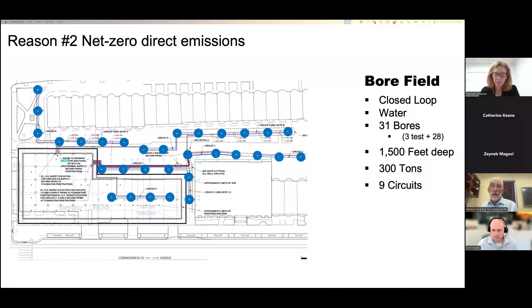The system is sized to provide 300 tons of cooling, or 90% of the thermal needs for the building. Electric backup boilers and chillers are designed to cover that last 10%. Early in the design process, the team looked at what it would take to do 100% of the thermal load of the building with geothermal. That would have taken 100 bores total, not 31, to get from 90% to 100%.